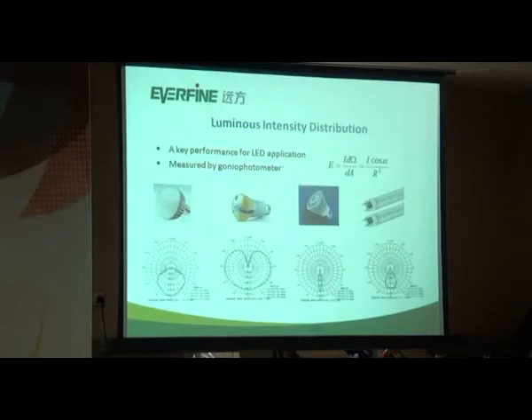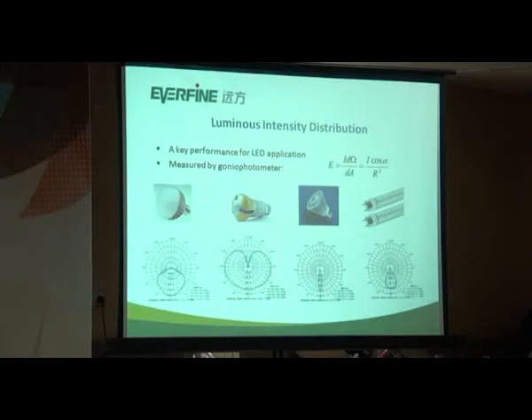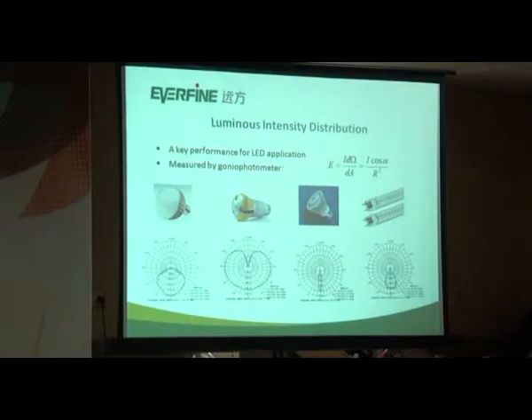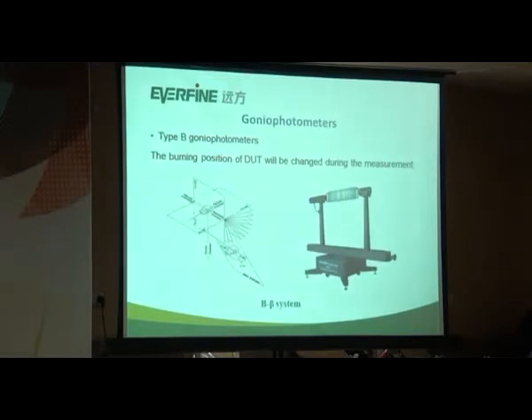Next, let's talk about another important quantity: luminous intensity. Luminous intensity distribution is very important in lighting design. The value of luminous intensity can be calculated according to the inverse square law from illuminance. As to measurement instrument, we could use a gonio photometer. According to CIE standard 121, there are three kinds of gonio photometer: Type A, Type B, and Type C. Usually the latter two are more commonly seen.